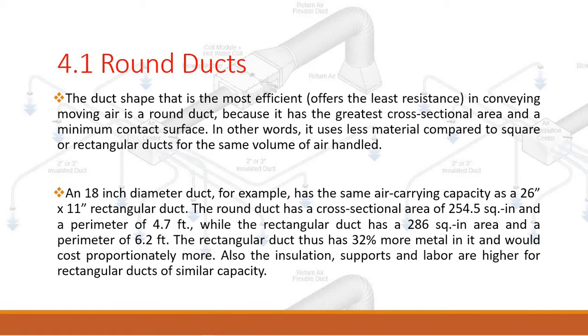Round ducts. The duct shape that is the most efficient and offers the least resistance in conveying moving air is a round duct, because it has the greatest cross-sectional area and a minimum contact surface. In other words, it uses less material compared to square or rectangular ducts for the same volume of air handled. For example, an 18-inch diameter duct has the same air carrying capacity as a 26x11 rectangular duct.